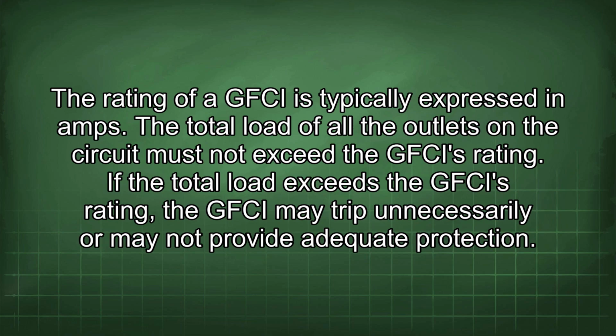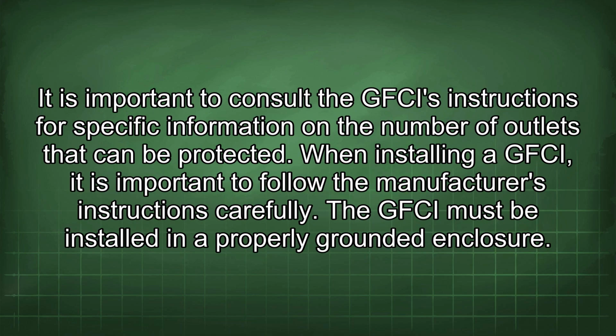The rating of a GFCI is typically expressed in amps. The total load of all the outlets on the circuit must not exceed the GFCI's rating. If the total load exceeds the GFCI's rating, the GFCI may trip unnecessarily or may not provide adequate protection. It is important to consult the GFCI's instructions for specific information on the number of outlets that can be protected. When installing a GFCI, it is important to follow the manufacturer's instructions carefully.